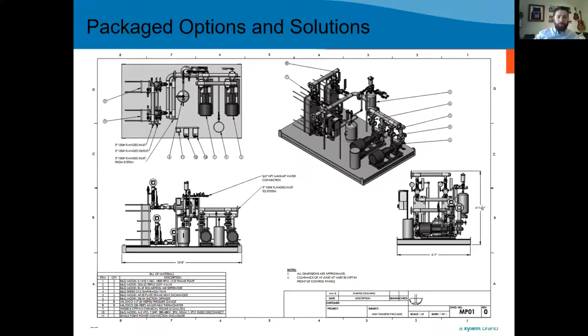The other thing we can do, again, we mentioned this at the top, packaged options and solutions. So this is a beautiful setup here. We brought in both pumps with the VFD, all your air separator components. We got a chem feed on this one. We got all your instrumentation installed properly, and a pair of plate and frames right on the back of the skid. Bring it right in. If you've got room for this, and generally new construction you do, I couldn't recommend this more. It's going to save you a lot of time, a lot of energy. Everything's certified and built properly. We've also done these where we'll put the inertia base just under the pump portion.